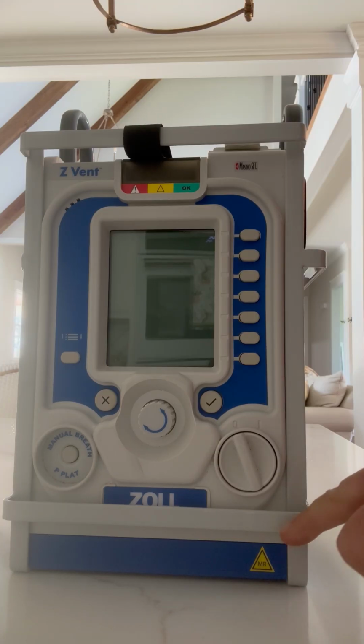This particular one is MRI conditional, and what that means for us is the 130 Gauss line. It needs to be outside the 130 Gauss line. So we have two forms of circuits. We have the 6-foot circuit for your regular transport, and then we have the 12-foot circuits for the MRI suite. The 130 Gauss line basically means 6 foot 6 inches away from the core of a 3 Tesla magnet. So having that 12-foot circuit will allow you to get outside of that range safely with the MRI stand, and it's always suggested to tether it if you can.